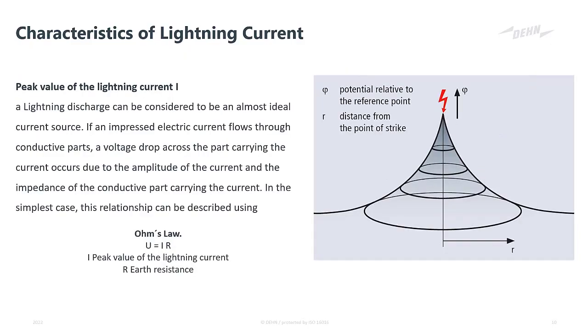If we look at the peak value of lightning current, it is important to understand that lightning is seen as an ideal current source, or an almost ideal current source. The impedance within a lightning strike is almost infinite. Now, when this current enters a conductor or a lightning protection system, there could be a voltage drop across those conductors and current carrying components within the lightning protection system. And if we do not control the massive voltage differences within a system, that could cause flashover to try and neutralize the voltage difference between the two. When the current also enters the soil, it creates a very large ground potential rise, and the ground potential rise measured in voltage can roughly be calculated by using Ohm's law, where the current coupled with the earthing resistance would give you the ground potential rise voltage.